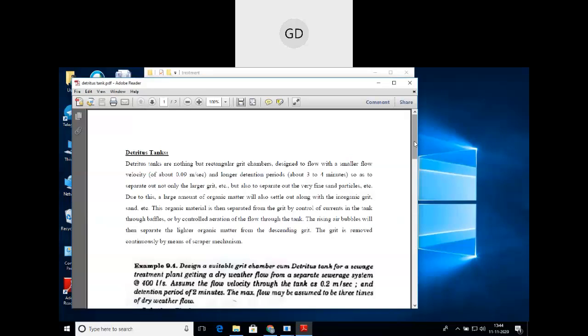These are rectangular grit chambers, and they are designed with a smaller flow velocity. The flow velocity is written as 0.09 meter per second. They have a longer detention period, like 3 to 4 minutes. In the aerated grit chamber, we had a detention period of up to 3 minutes.